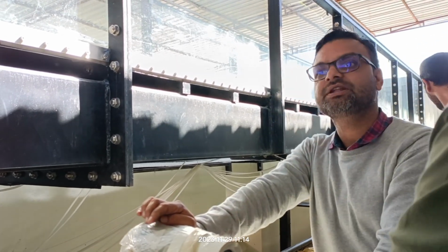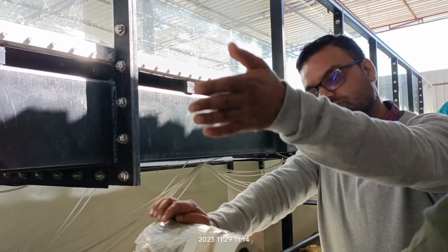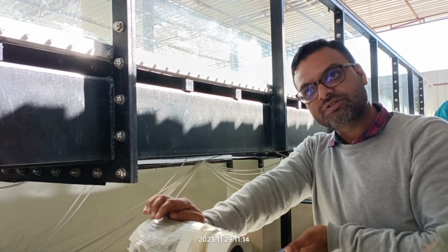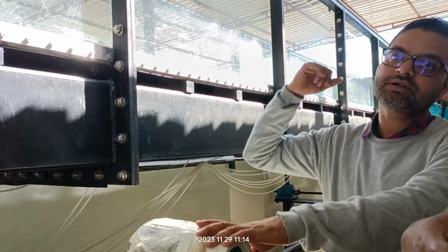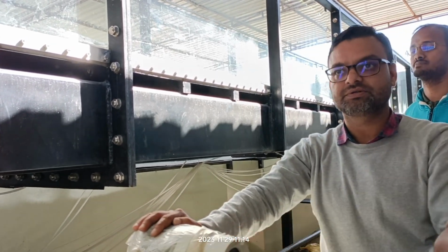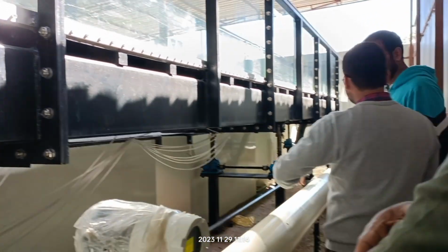So in that principle, this electromagnetic. So higher the velocity of the flow water, higher will be the voltage. So that voltage is calibrated in terms of metric cube per hour. Okay. Then after that, with the help of this hose pipe, it goes into the inlet side.